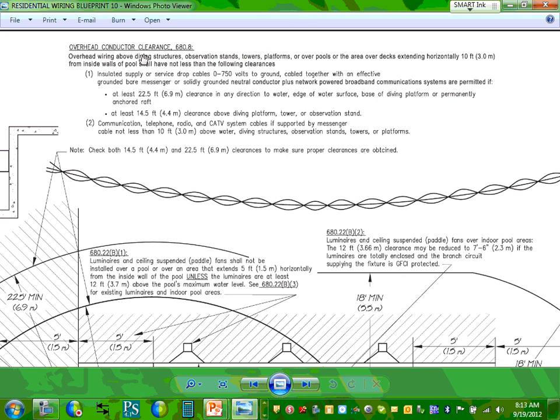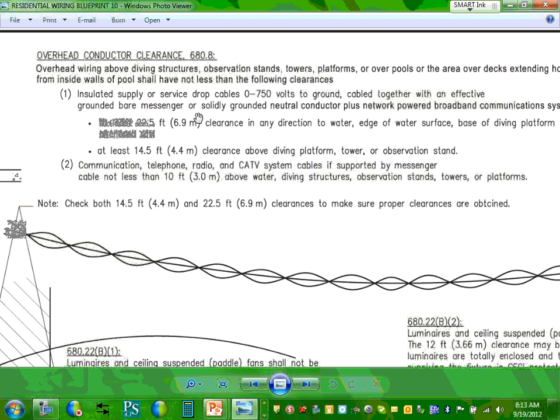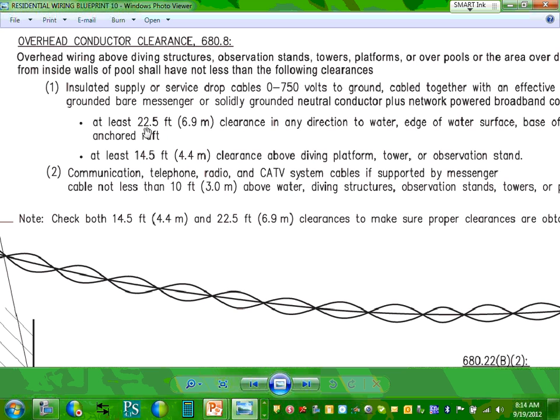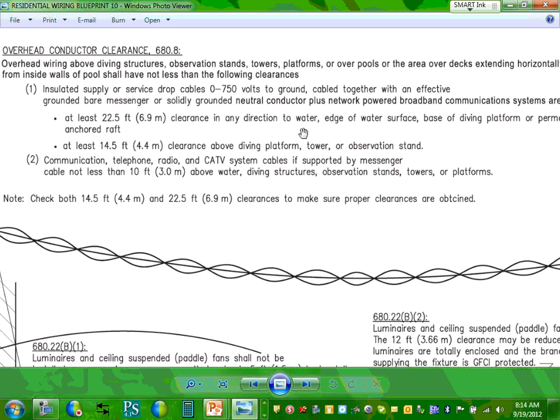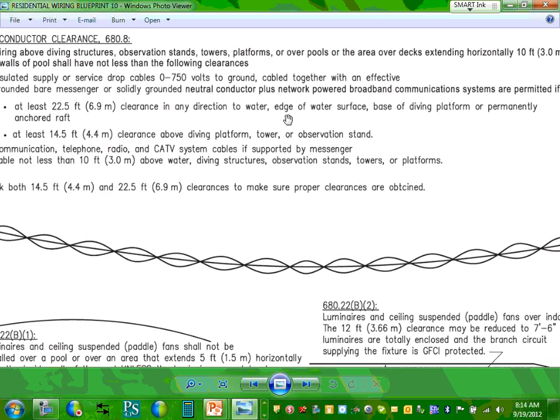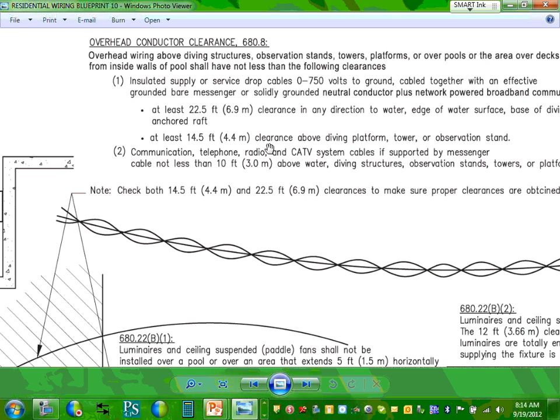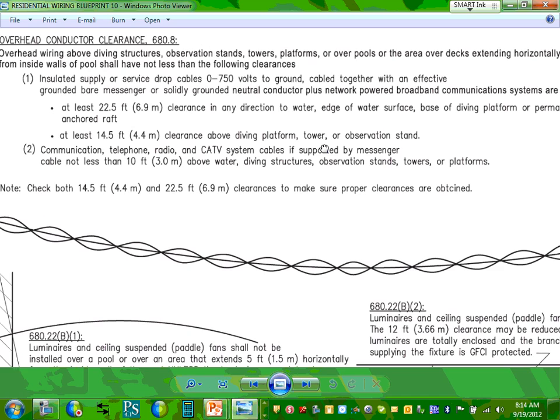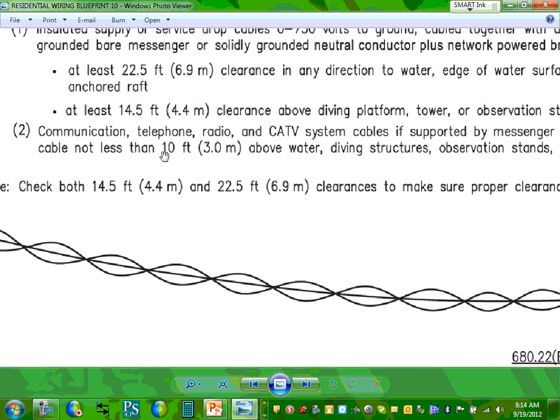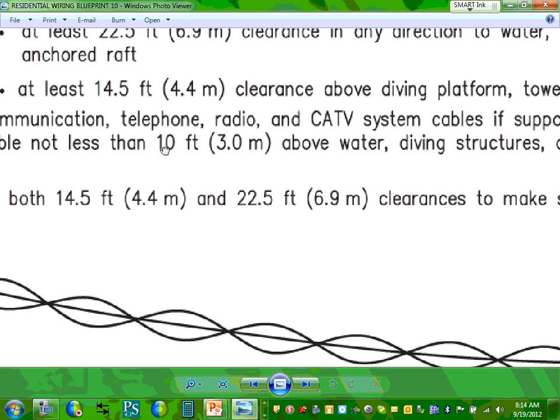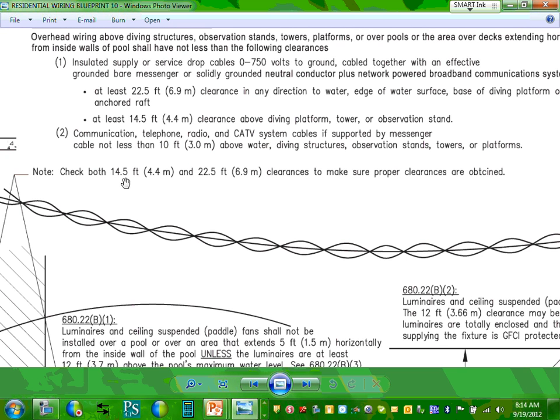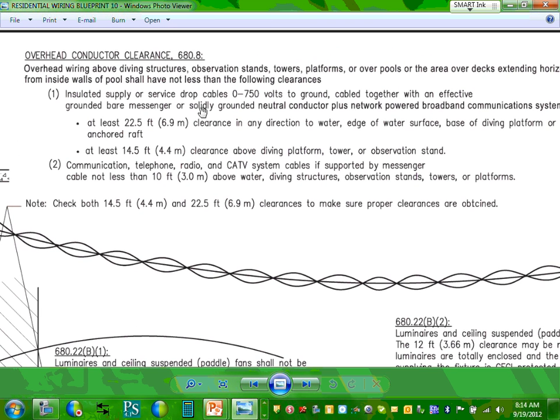Let's talk about power lines over swimming pool. They give you clearances. Can I bring a power line over the swimming pool, right at the top of the swimming pool? No problem. If your voltage, look at that, insulated conductors, up to 750, here's the clearances, 22.5 clearances in any direction away from the edge of the swimming pool, and at least this amount clearances above diving platform. Communication, if you have communication cable like phone, can you guys see the number that you have to maintain? 10 feet. So anyway, and all these guys becomes a big deal.